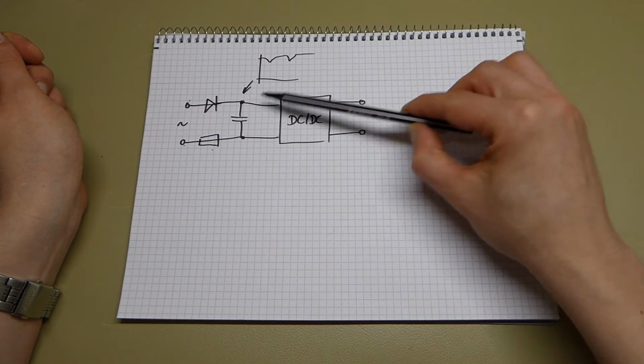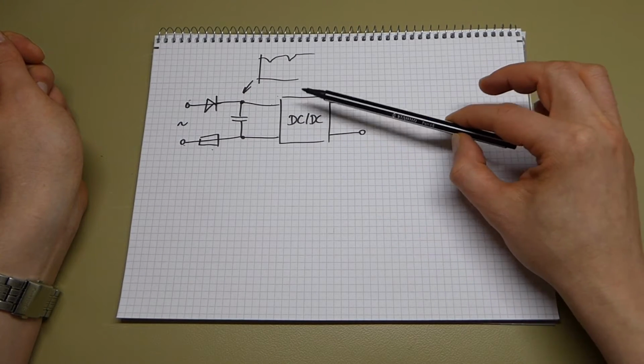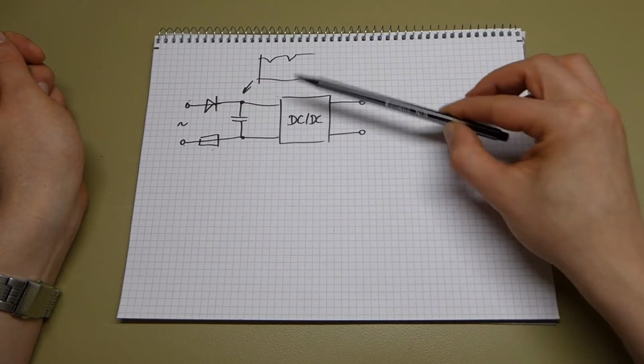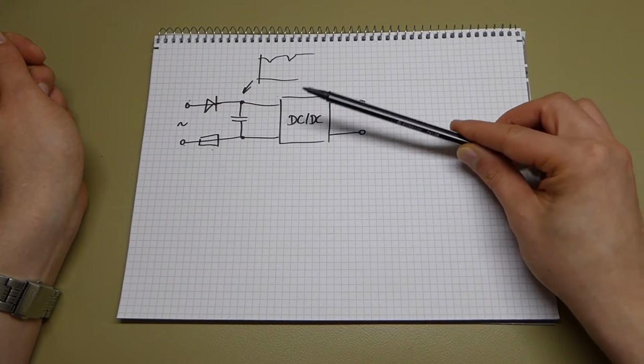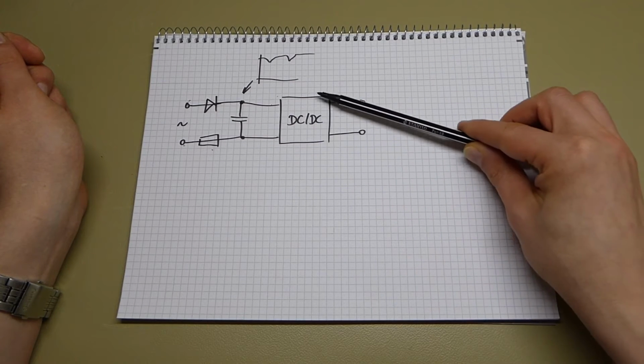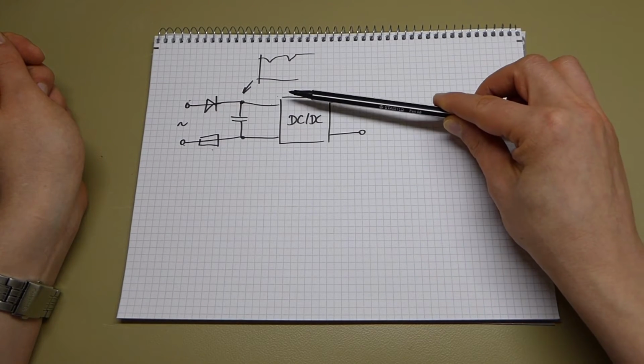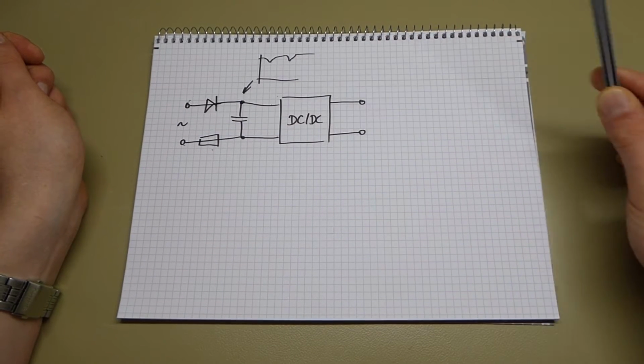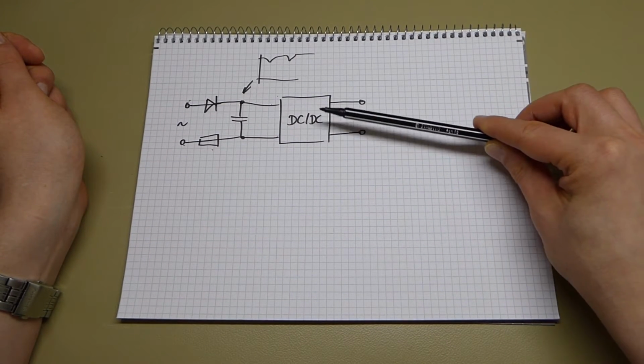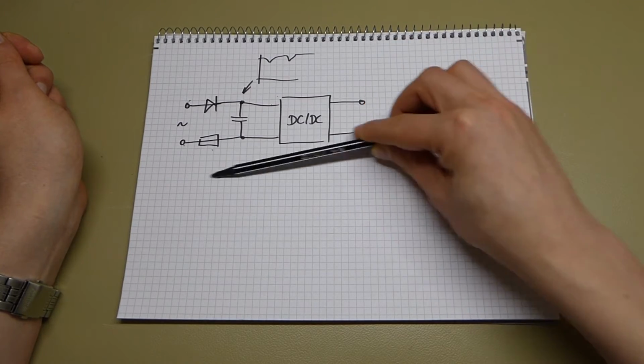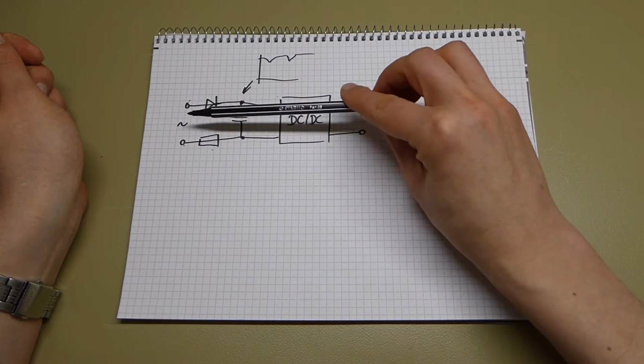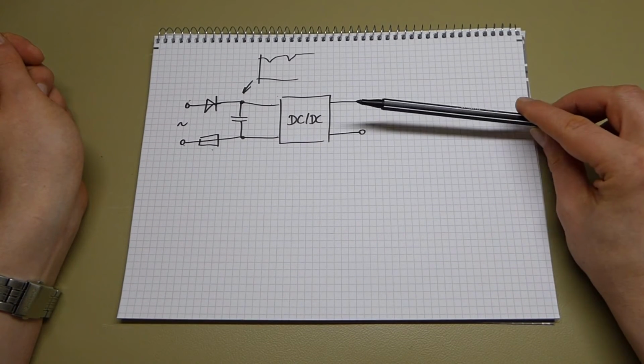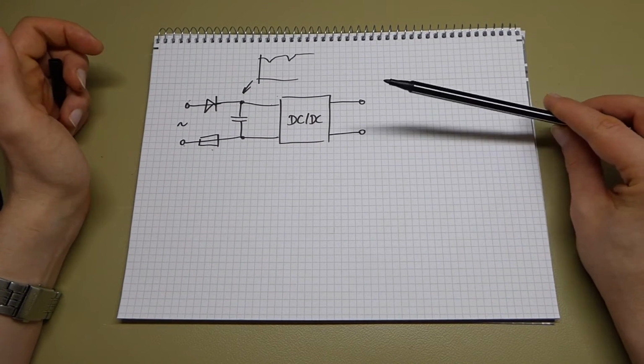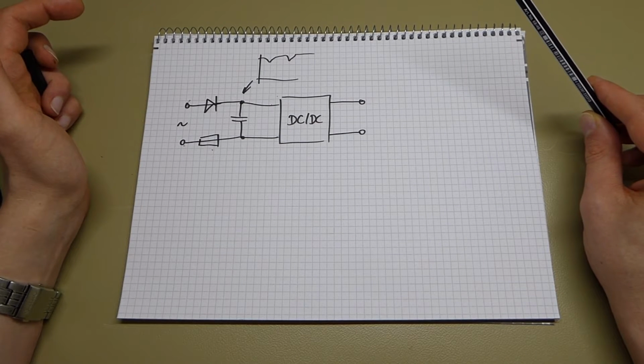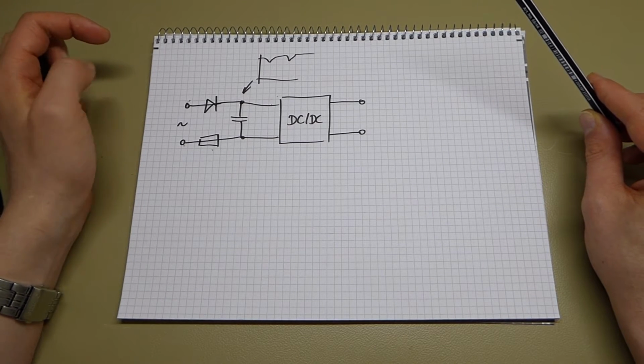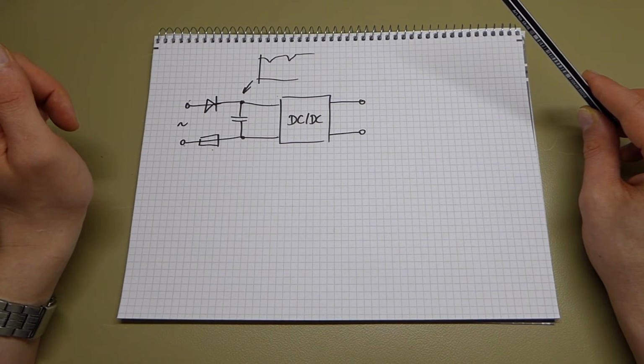So you need to be aware that you might no longer have the overcurrent protection from the fuse. And finally, our simplified model obviously assumed that this DC-DC converter is very simple and there's nothing else around. Obviously you have things like active power factor correction, or this converter could look at the actual input frequency to make sure it's within specifications. So if there's anything in here, or in the front, that relies on there being an AC input, then obviously this whole thing won't work off DC at all. But as I said, in principle you could run most AC switch mode converters off DC if you're aware of the issues you might encounter.